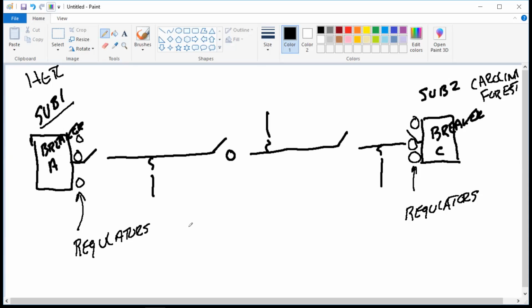So, and I'll put them in the notepad too. So breaker A equals non-automatic. Okay, you'll have to set up both breakers in the same fashion. Breaker C, and they'll specify the substation on the radio. Non-automatic. How are they doing this? What system are they using? SCADA. Yeah, they're doing this all by SCADA. They have to do verbal confirmation over the radio. They're telling you this over the radio, but they're doing it all by SCADA, and you're following steps on a form in the process that's going on. So you're just sitting there in the truck listening.